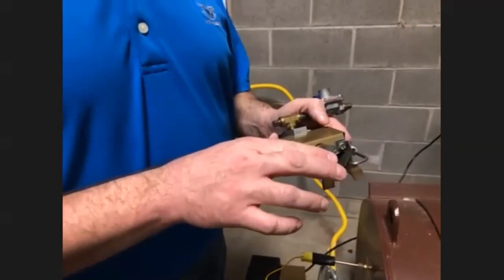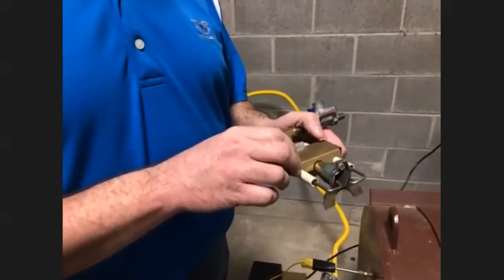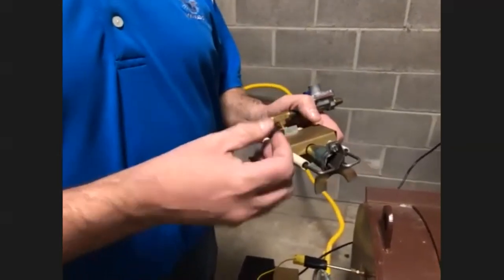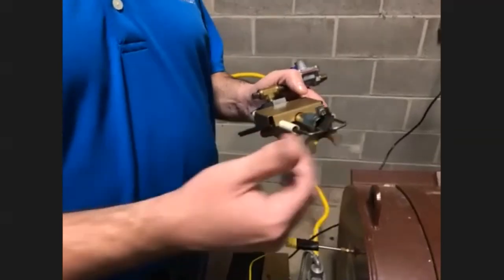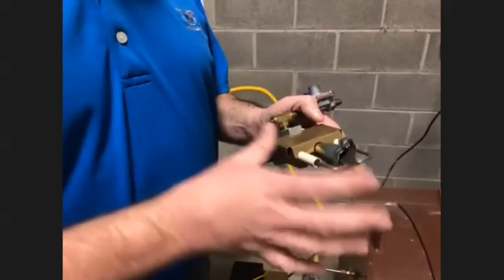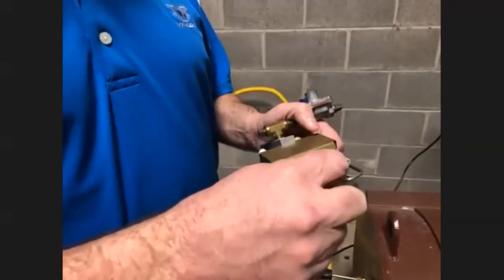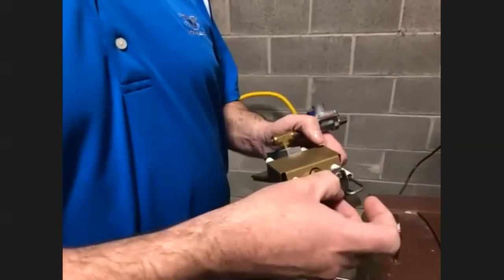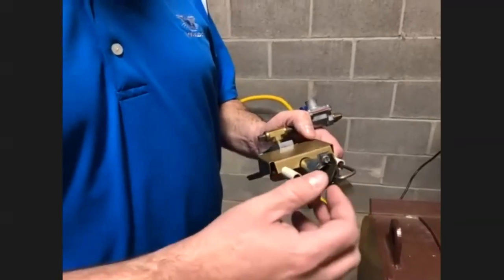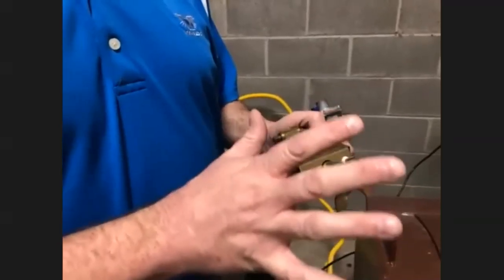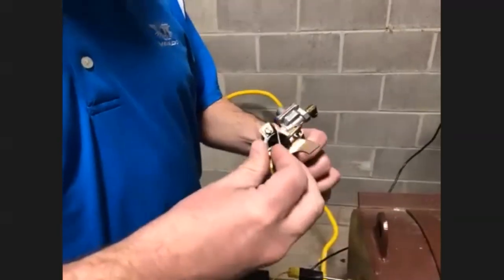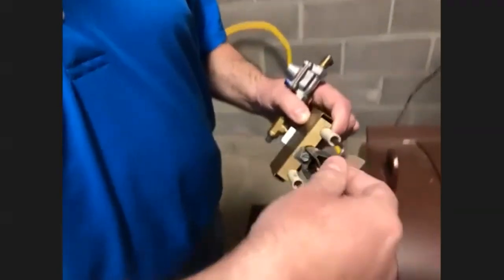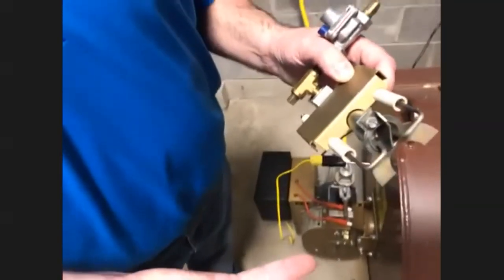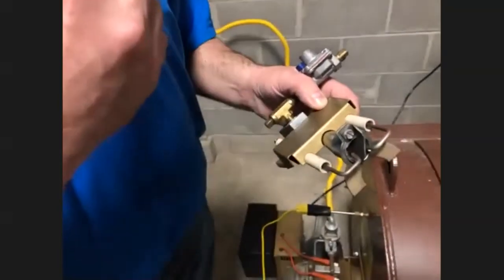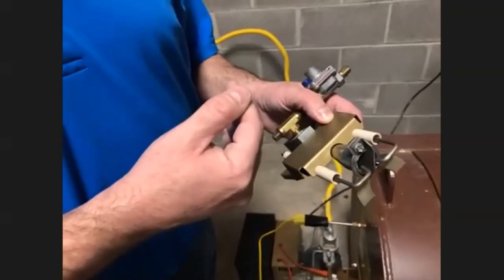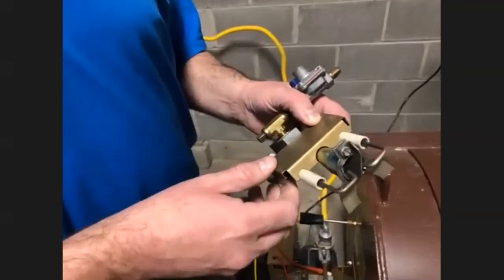When you get that carbon buildup in wet, moist climates, like in the spring when you're getting a lot of dew in the mornings, if that carbon buildup gets wet, it will prevent the spark from jumping. That is the highest maintenance issue with gas burners. You need to make sure those tips are clean and dry. Again, that is the most common issue you will have with gas burners. If you keep those clean and dry, you may have to periodically take an emery cloth and clean them up a little bit, and you're fine as long as everything's clean and dry. Sometimes they may just be a little wet more than they are sooted up. Keep them dry and that spark will work for you.